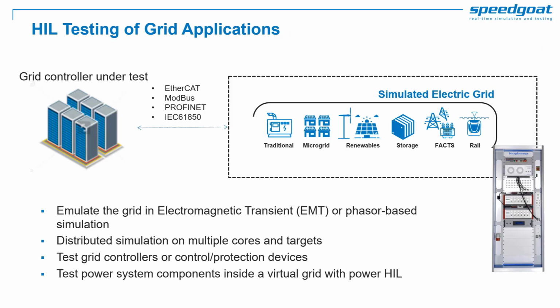Grids typically involve a controller and some protection devices. Real-time testing enables us to test such controllers safely. For that, we are going to emulate the grid in electromagnetic transient (EMT) or phasor-based simulation, and perform distributed simulation on multiple cores and targets. This enables us to test grid controllers or control protection devices. To connect the controller to the simulator, we use I/O protocols such as EtherCAT, Modbus, Profinet, or IEC 61850. We can also test power system components inside a virtual grid with Power HIL.